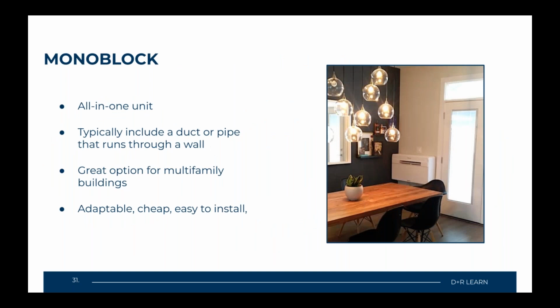All right, so we just got through with your VRF systems. Let's talk a bit about the monoblocks. Your monoblock system is a comfort heating and cooling system where all the components of the system are packaged together inside a single unit or box. It's similar to the heat pump water heater we spoke about earlier, situated in the utility closet where all the components are put together. These may also be called package terminal heat pumps. Monoblocks are great options for multifamily buildings or buildings with several zones that have individual heating or cooling needs. You can typically have these systems mounted on the wall, ceiling, or floor, and they require ventilation to the outside of the building.